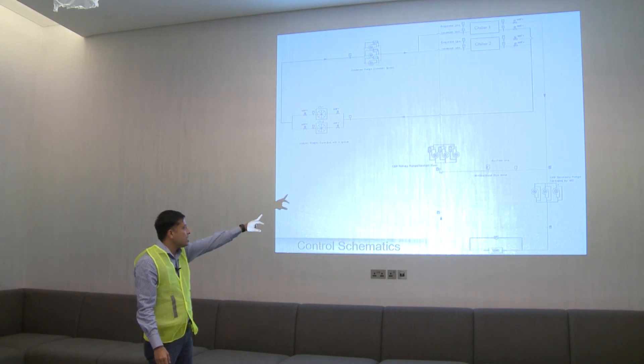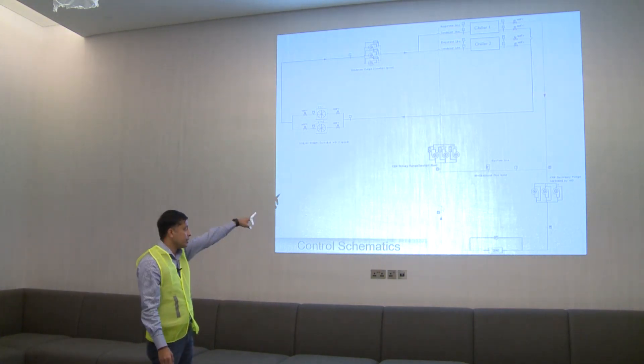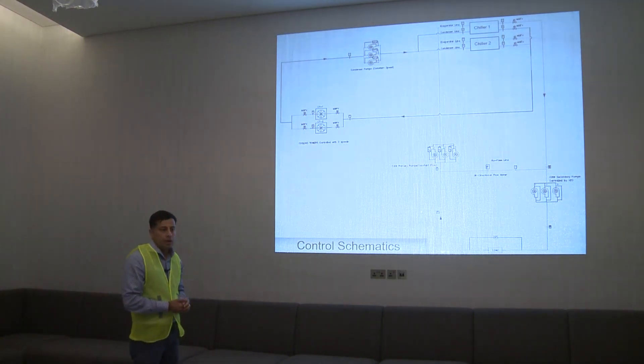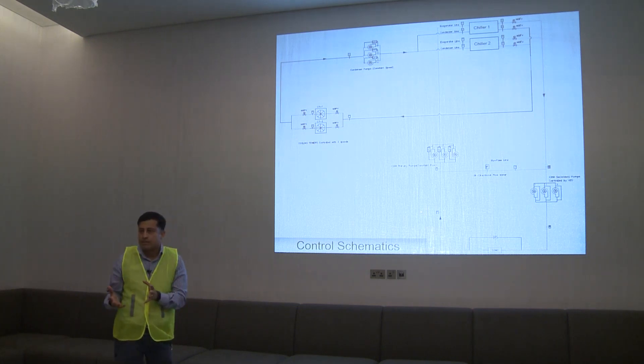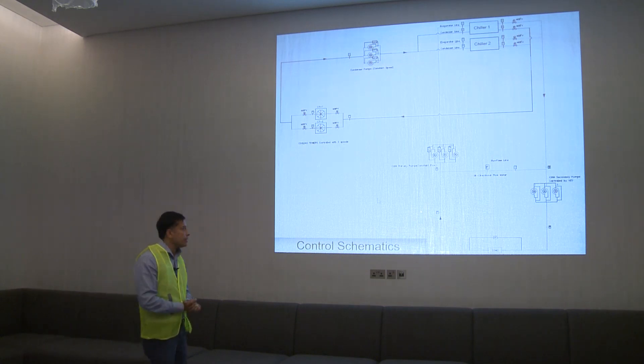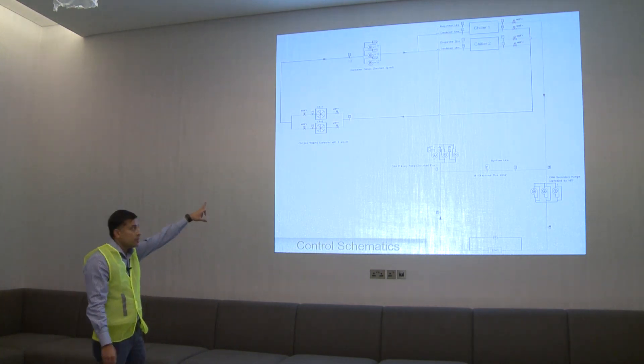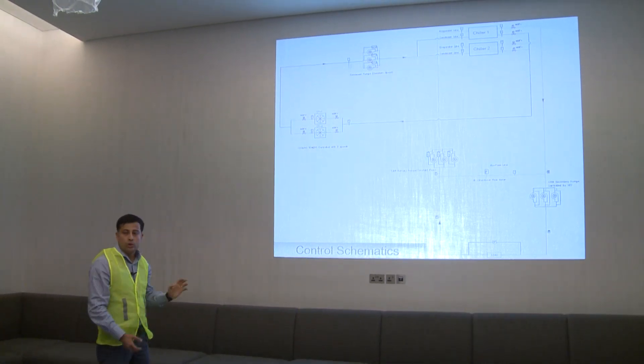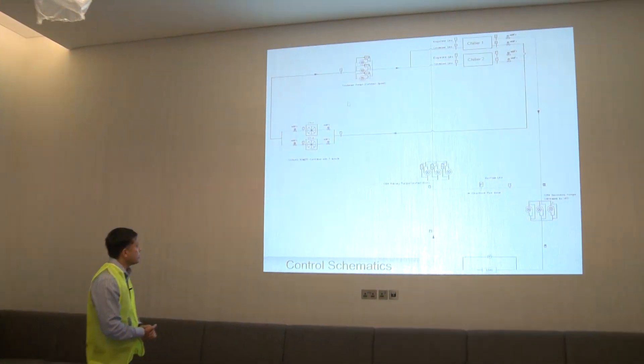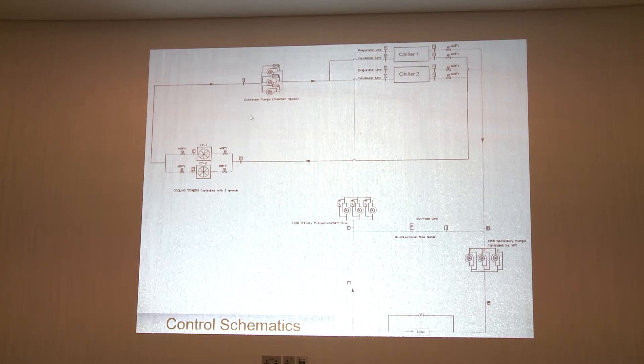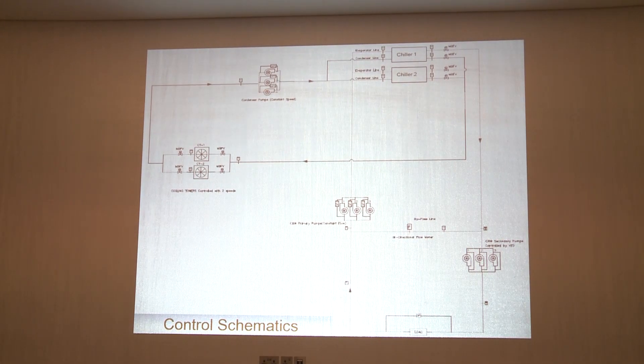The load supply temperature sensor, the chiller return temperature, and the cooling tower supply temperature at the common header are the three critical temperature sensors in the system. If anything happens to these sensors, you should take immediate action to maintain the system in the best condition and keep it running in auto mode.